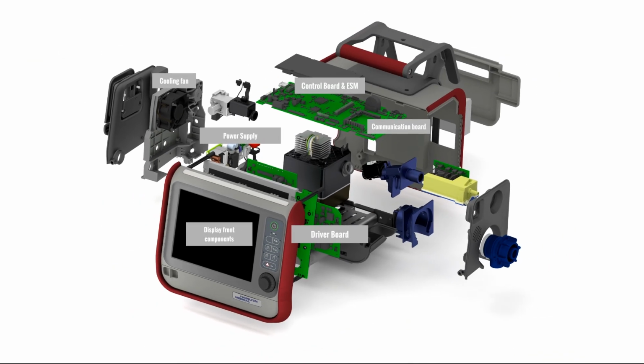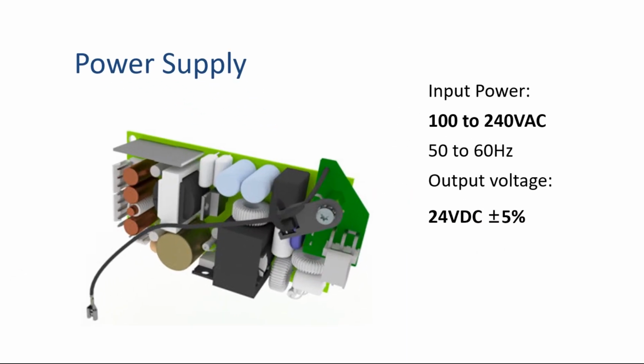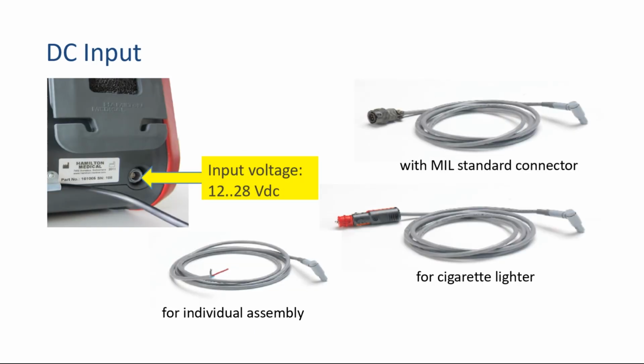Next, we will see how power management is implemented. The power supply's input power allows voltages of between 100 and 240 volts AC with 50 to 60 Hz. The only output voltage is 24 volts DC. In addition to the AC input, the Hamilton T1 also has a DC input. The input voltages allowed are between 12 and 28 volts DC. Various cable connectors are available for different uses in the field.